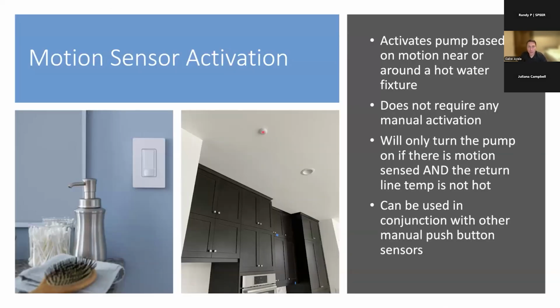There's also a motion sensor activation. If you don't want to have a manual switch, you can use an occupancy sensor, and the pump only turns on when somebody walks in front of that motion sensor. But also keep in mind that because we have the temperature sensor, as long as hot water is in the line, even if people keep walking past the occupancy sensor, the pump isn't going to keep turning on. Once hot water is satisfied, the pump stays off.